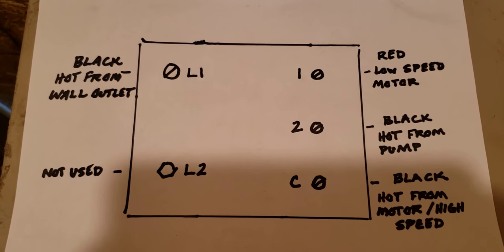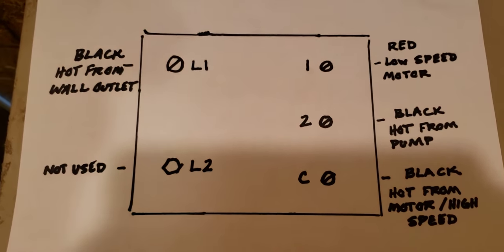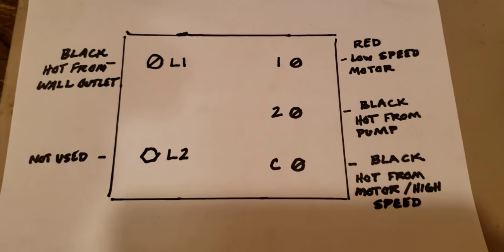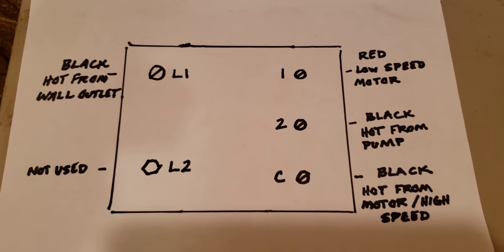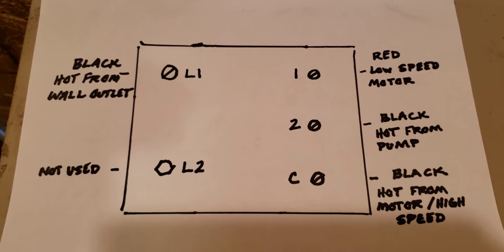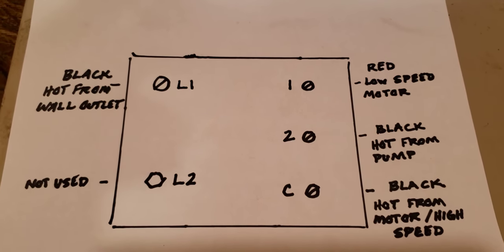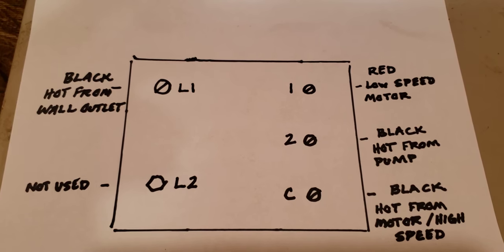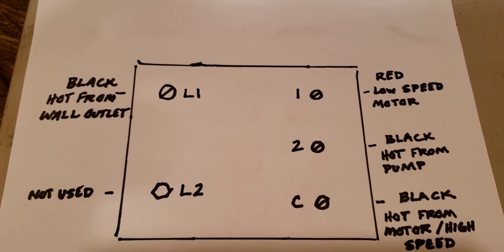The black hot wire from your pump will go to number two, and the black hot wire from your motor, which is your high-speed motor wire from your motor, is going to go to C.